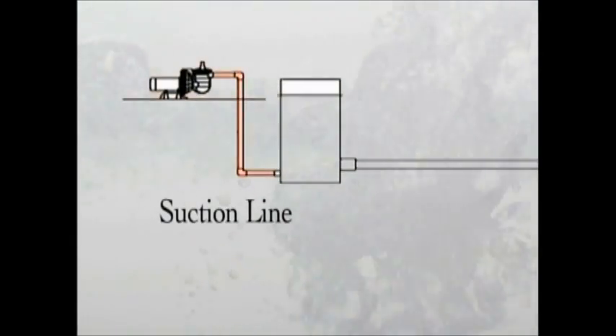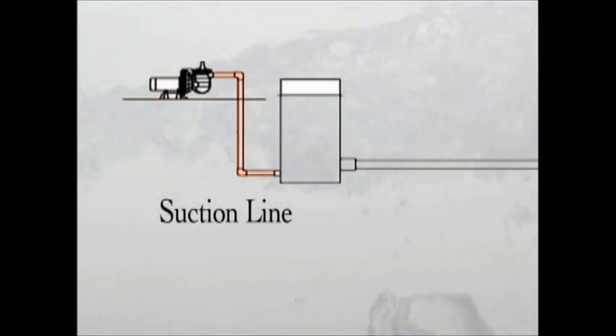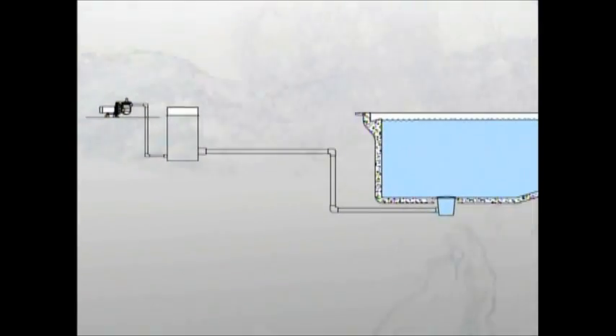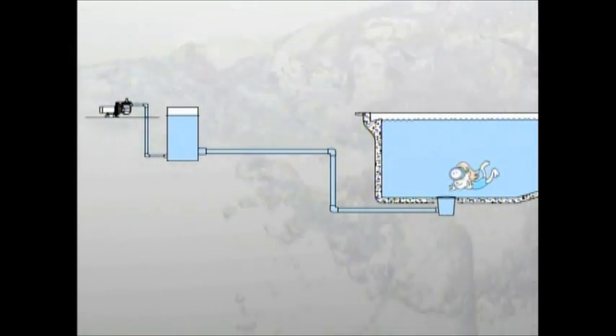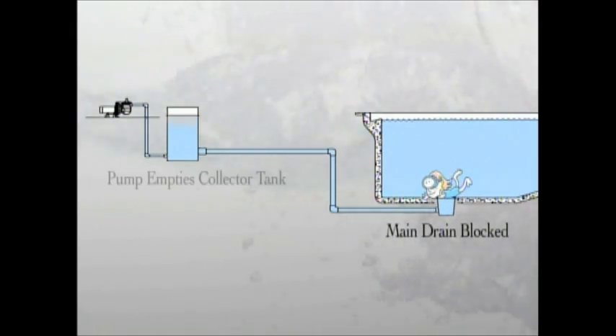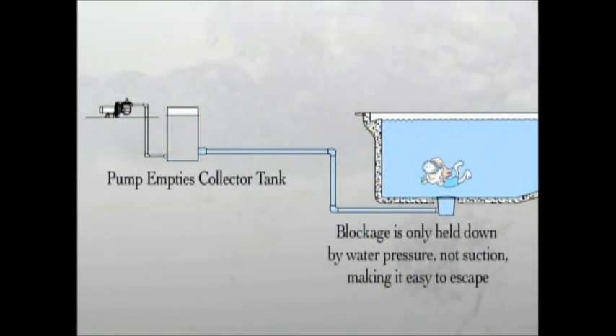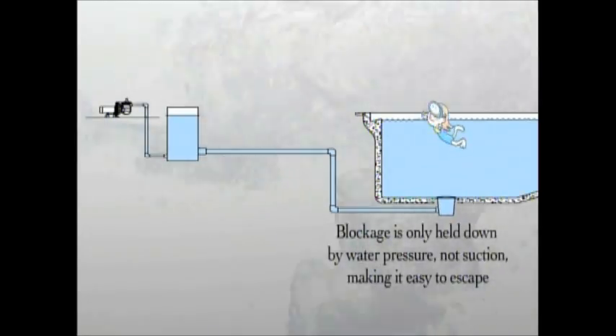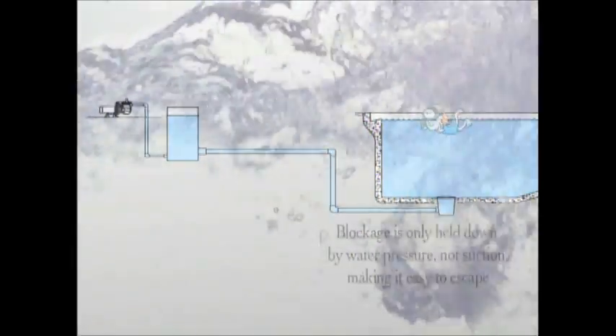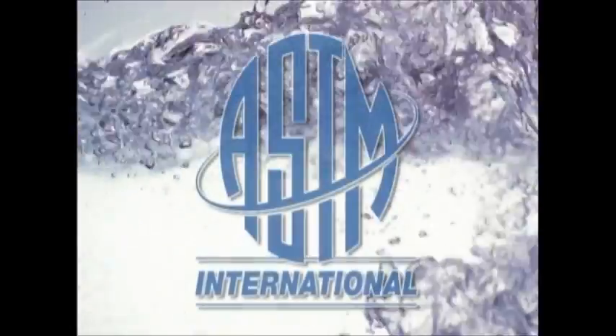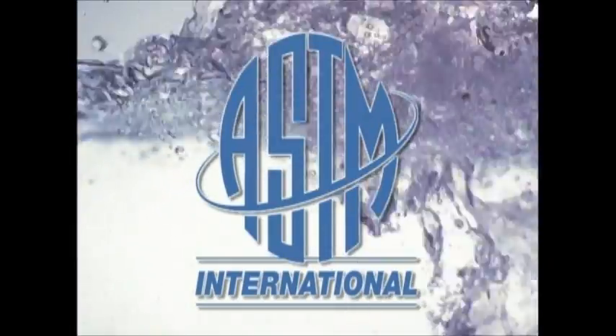The suction line from the pump is connected to the collector tank, not the main drain. When the pump is turned on, water flows from the main drain in the pool to the collector tank by gravity, and from the collector tank to the pump by pump-created suction. With this type of system, the main drain is not a source of suction from a pump. Because of Florida's perfect record of no suction entrapments recorded on gravity flow systems using collector tanks, an ASTM standard for collector tanks is being written.